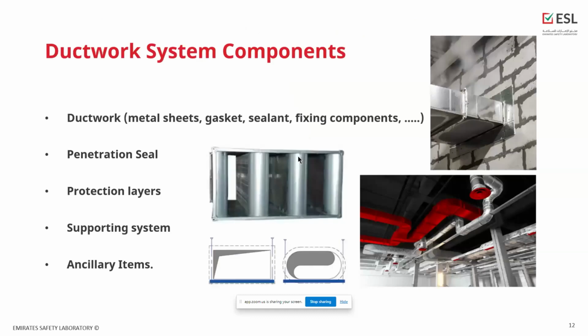Okay, so the components of the ductwork system: normally we have the ductwork itself, which includes the metal sheet, gasket, sealant, and fixing components like rivets. And we also have a very important part of the system, which is the penetration seal, just to protect the passing through the building elements, like when the duct is passing through the wall, partitions, roof, or the floor, we need to protect the passing through.